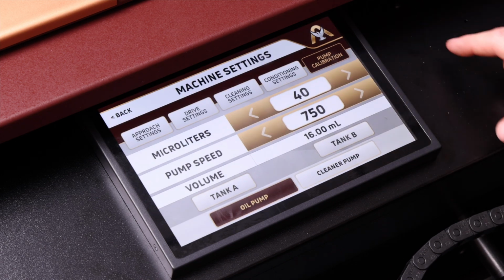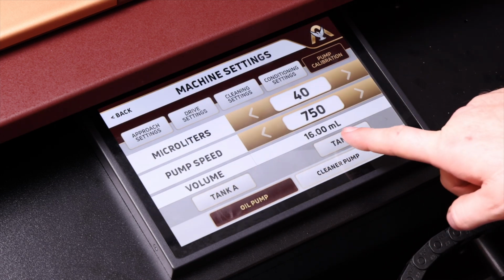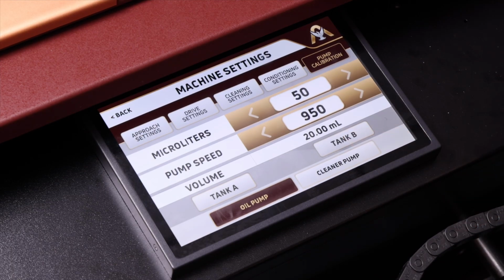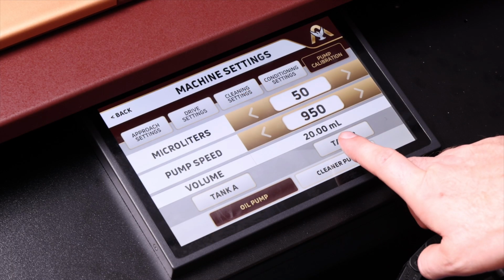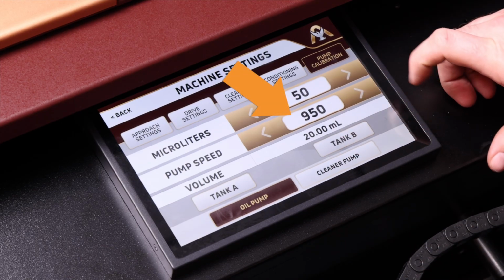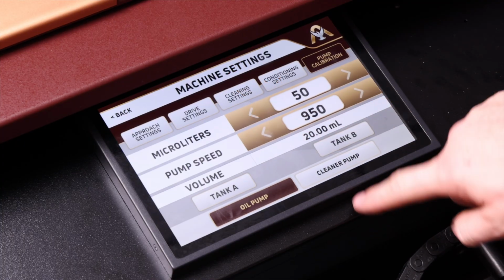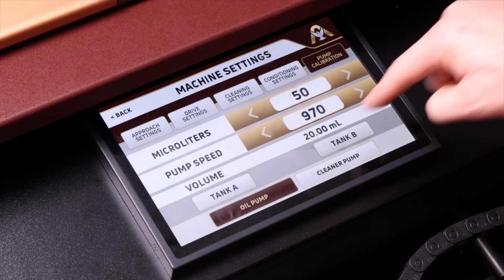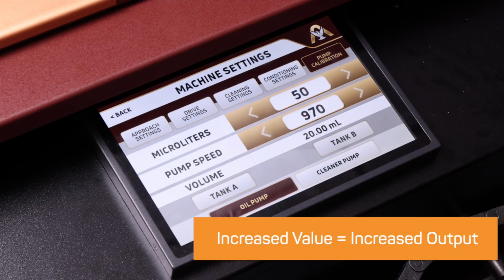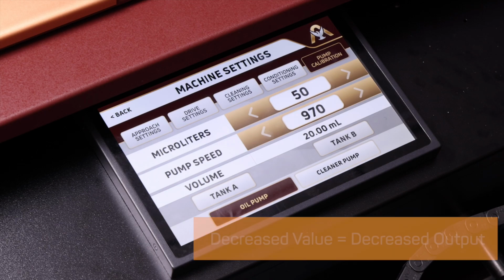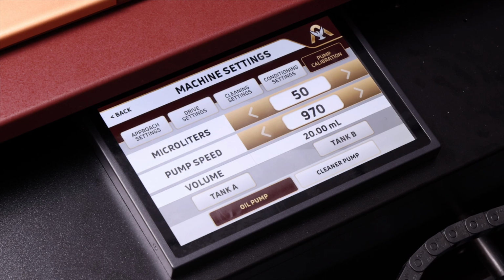As you change the microliter settings, you'll notice the volume changes with the microliters as well. If for any reason you are not getting the desired volume, then we would adjust our pump speed. You can adjust by the arrows or by the numeric keypad. Increasing the value will increase the amount dispensed. Decreasing the value will decrease the amount dispensed. Run the calibration test on the desired microliter until the correct volume is reached. As a reminder, changing the pump speed value will adjust both pumps as they are both driven by one stepper motor.